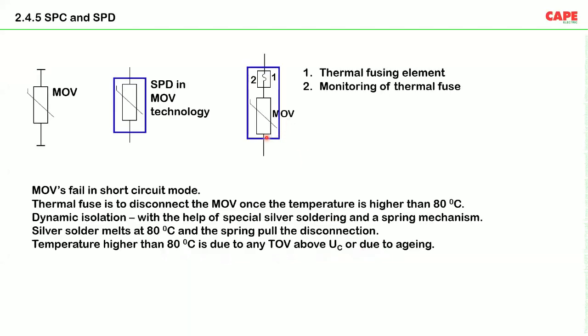So basically, an MOV based SPD means it has an MOV plus some safety features integrated inside. It has a thermal fusing element, and nowadays SPDs also have an HRC fuse inside. Once it comes to the market, this particular part, the silver soldering and the spring mechanism, is the very critical part of an MOV based SPD. That means the efficiency of this protective mechanism predominantly decides the cost of that particular SPD.